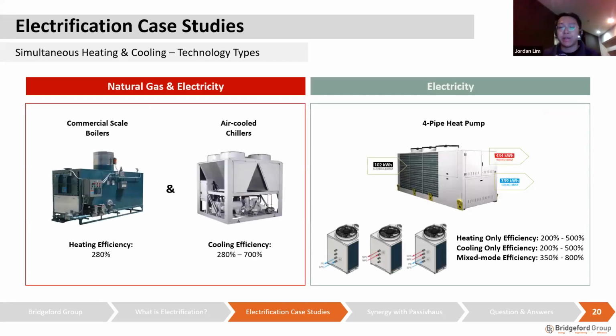Sorry, moving on, I also want to share a little bit about the findings that we found for 4-pipe heat pump technology, which is a heat pump system that can supply both heating and cooling simultaneously. It can also supply heating only and cooling only as well. So if a development has both boilers and chillers, they can consider using a 4-pipe heat pump instead.